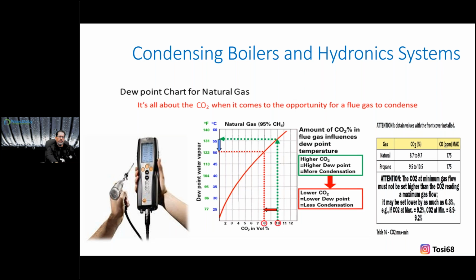The green line here shows you the dew point. CO2 volume percentage of 10 - I have a range, it goes from 8 to 10, that's the dotted line in red. But look at the water temperature now - the green is roughly 133, 35, let's call it, down to about 122. This is the returning water temperature, the flue products leaving. If I set it to 8, I'm waiting longer now to collapse the flue products to get that higher efficiency.